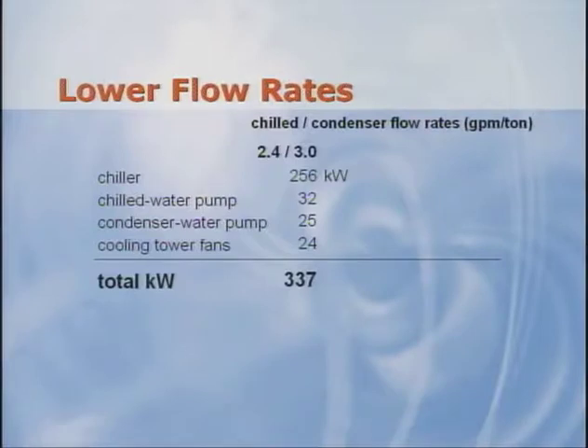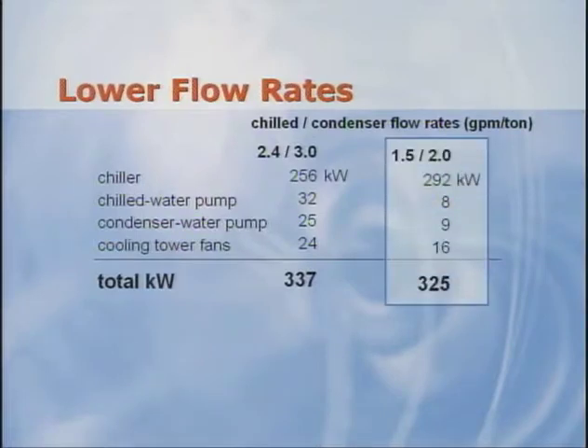One such opportunity is the selection of design flow rates for both the chilled water and condenser water sides of the system. This slide shows an example 450-ton chilled water plant using conventional flow rates of 2.4 GPM per ton on the chilled water side and 3 GPM per ton on the condenser side. The table shows the kW draw of the chiller compared to the pumps and cooling tower fans. Now see what happens when the same system is designed for lower flow rates. Consistent with the recommendations of the ASHRAE Green Guide, the flow rates are reduced to 1.5 GPM per ton on the chilled water side and 2 GPM per ton on the condenser side. The chiller consumes more power, but look at the drastic reduction in pump and tower energy. These reductions more than offset the increase in chiller power. In fact, the full load power draw of the overall plant is reduced by 4%, and the savings can be even larger at part load conditions.